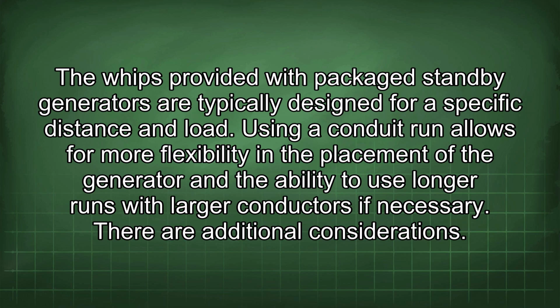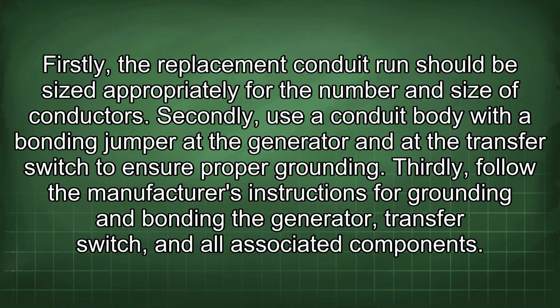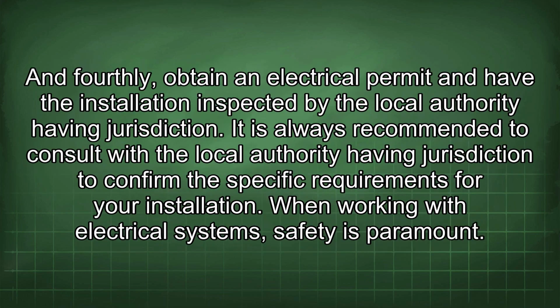There are additional considerations. Firstly, the replacement conduit run should be sized appropriately for the number and size of conductors. Secondly, use a conduit body with a bonding jumper at the generator and at the transfer switch to ensure proper grounding. Thirdly, follow the manufacturer's instructions for grounding and bonding the generator, transfer switch, and all associated components. And fourthly, obtain an electrical permit and have the installation inspected by the local authority having jurisdiction. It is always recommended to consult with the local authority having jurisdiction to confirm the specific requirements for your installation.